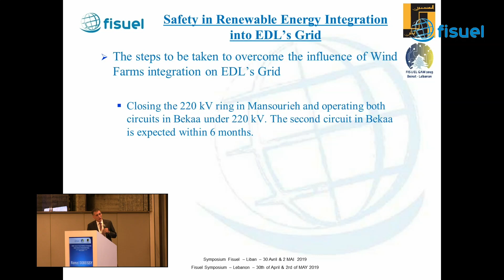The steps that should be taken to overcome the influences of wind farms integrated on EDL's grid are: first, closing the 220 kilovolt ring in Mansouriye and operating the second circuit at 220 kilovolt in Bekaa. The second circuit in Bekaa is expected within the coming 6 months.